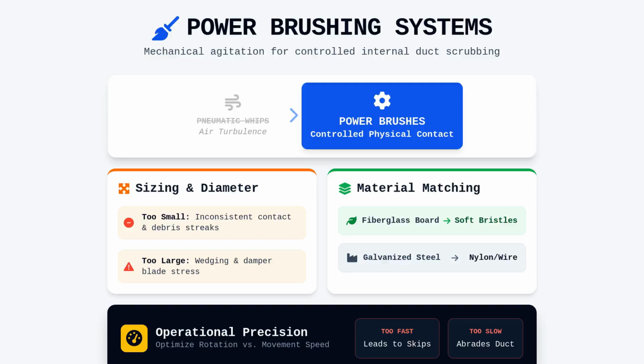Power brushing systems represent a mechanical alternative where physical contact is the primary mechanism for agitation. Unlike pneumatic whips, which rely on the turbulence created by escaping air, brushes offer a controlled method for scrubbing internal duct walls. When selecting a brush, the diameter relative to the duct size is the most important variable to consider. A brush that is too small for a large duct will fail to make consistent contact with all four sides, leaving streaks of debris, while one that is too large can become wedged or cause undue stress on the damper blades and turning vanes. You should match the bristle stiffness to the material of the duct.